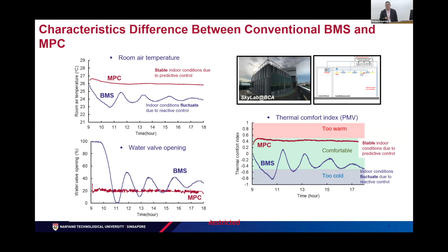inside the room. And if you look at the third graph, which is the thermal comfort index, or the PMV as we know it, the predicted mean vote. Obviously the optimum condition is 0, which is the thermal neutral value for the PMV. In case of BMS, you can see that the thermal comfort is varying from comfortable to not so comfortable zone. And in case of MPC, you have a very steady thermal comfort index for your occupants. And this is how MPC is able to save energy by minimizing the energy wastages that typically occur in your conventional PID systems.